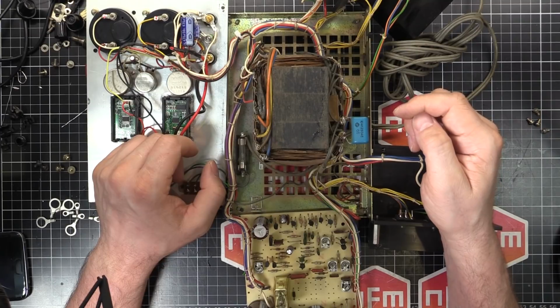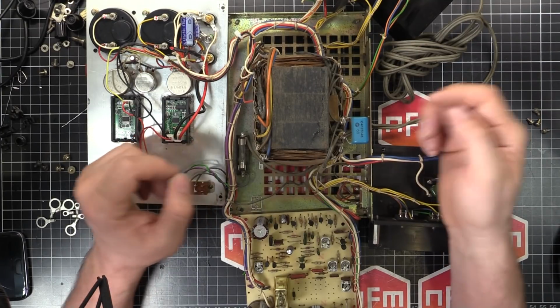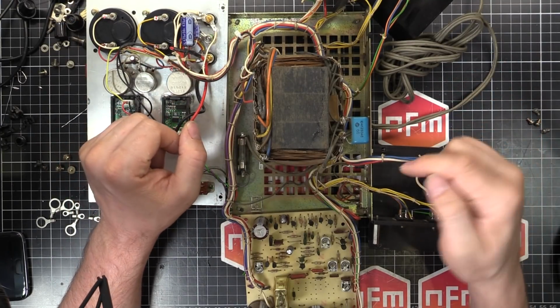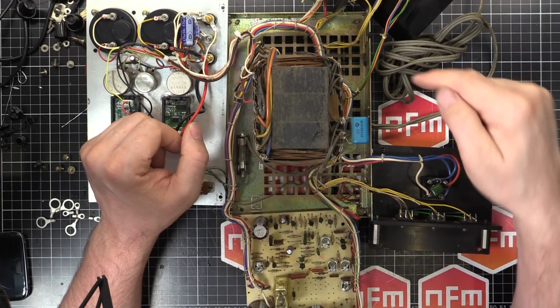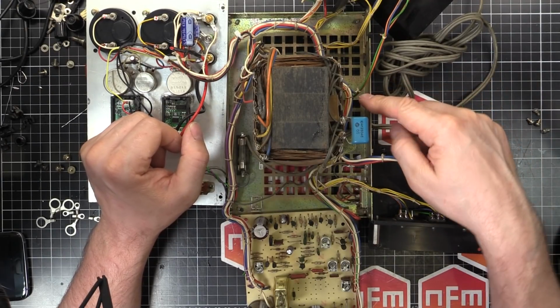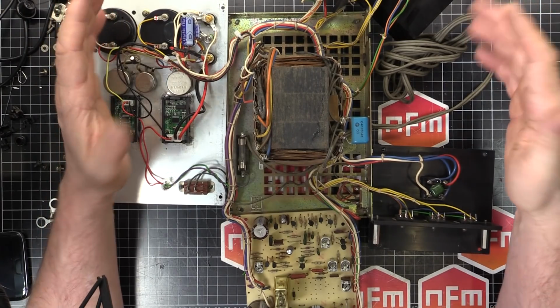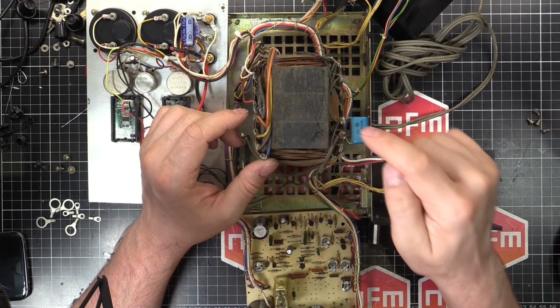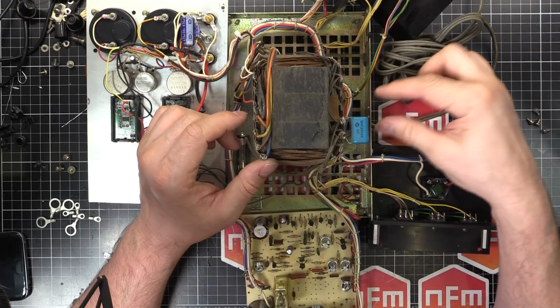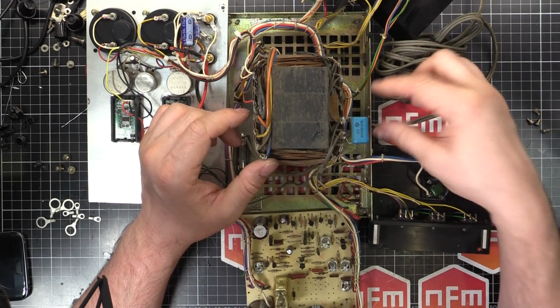Whereas a Y-class will always fail open - well, in theory it will fail open, because a Y-class is used between the line and the chassis earth. If that fails short, it can live on the chassis, which is no good.